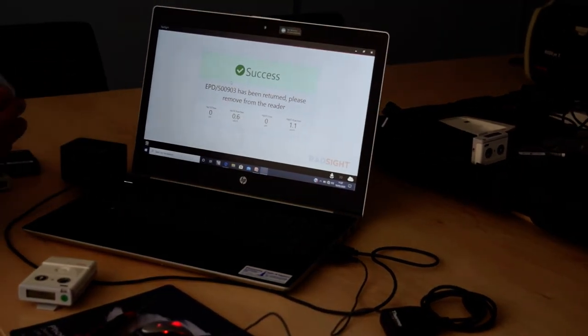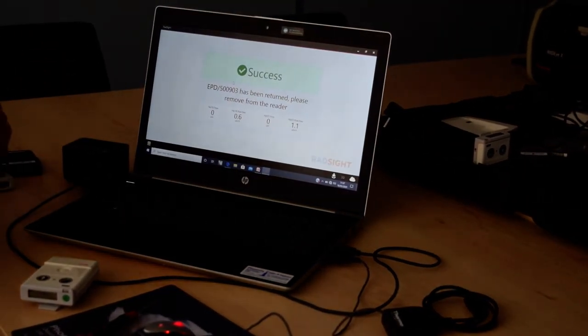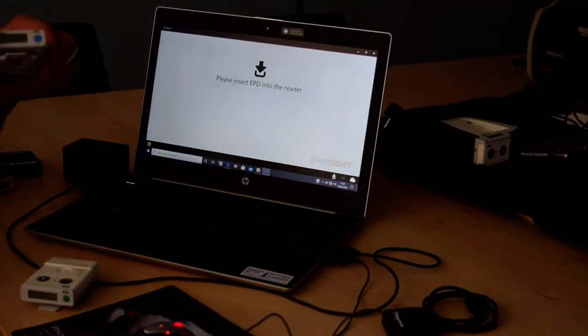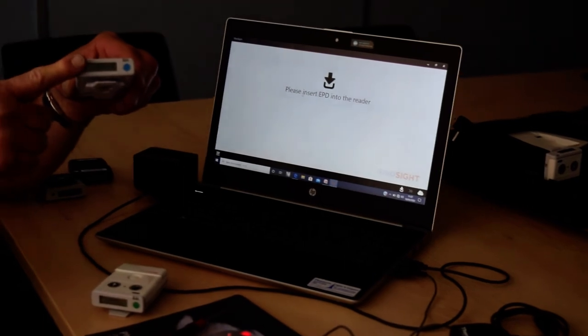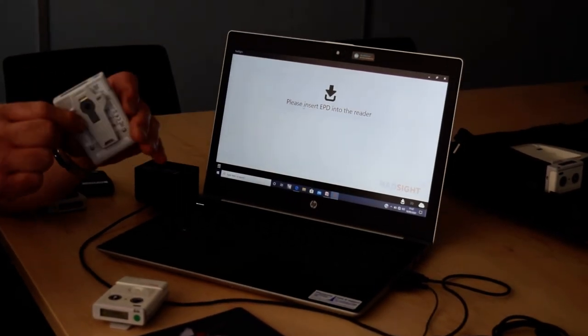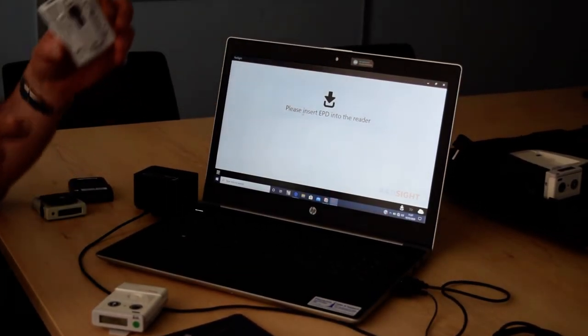When I remove it from the reader, the dosimeter has now been reset to zero, and it's also been switched off, ready for the next reissue.